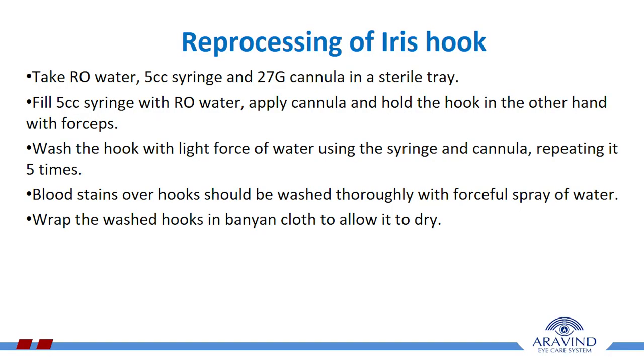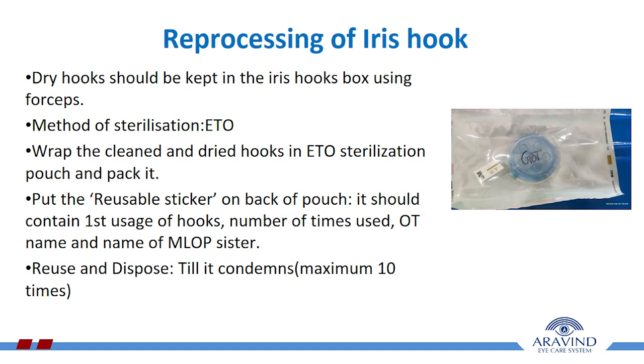Reprocessing of iris hook. Take RO water, a 5 cc syringe, and a 27 gauge cannula in a sterile tray. Fill the 5 cc syringe with RO water, apply the cannula and hold the hook in the other hand with forceps. Wash the hook with light force of water using the syringe and cannula, repeating it 5 times. Blood stains over hooks should be washed thoroughly with forceful spray of water. Wrap the washed hooks in a banyan cloth to allow them to dry. Dry hooks should be kept in the iris hooks box using forceps.